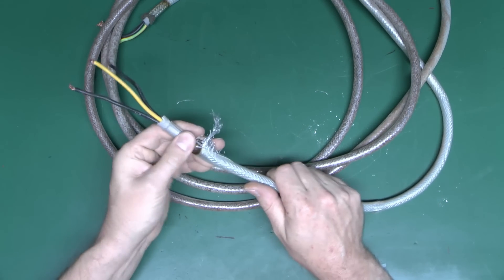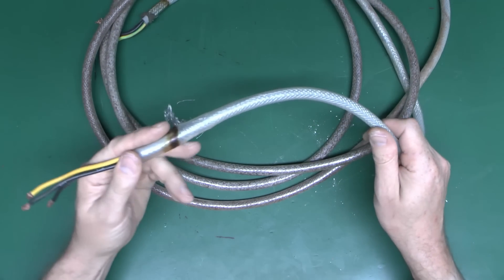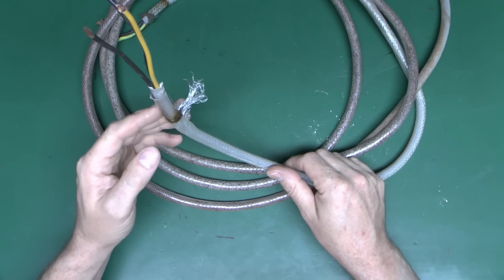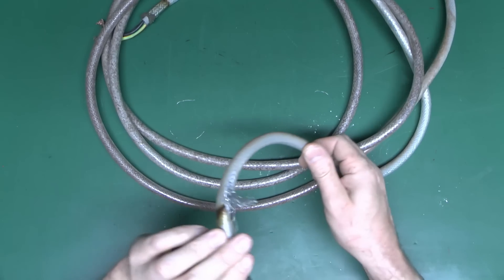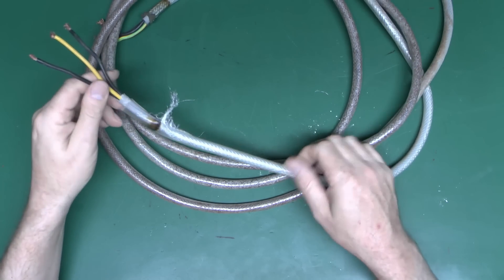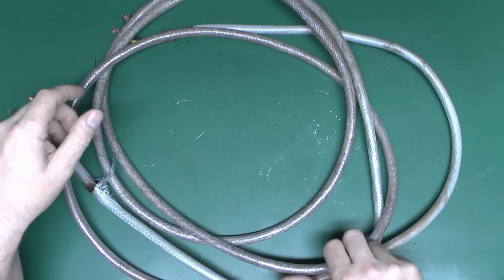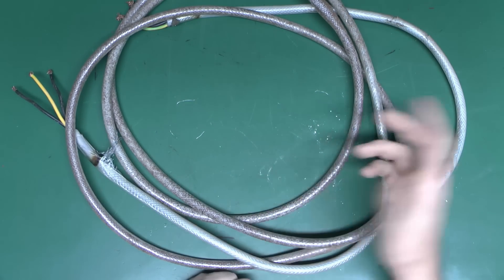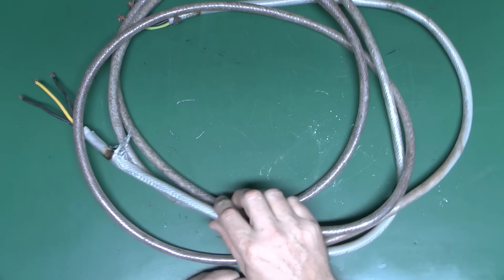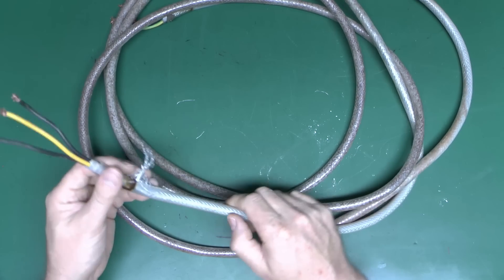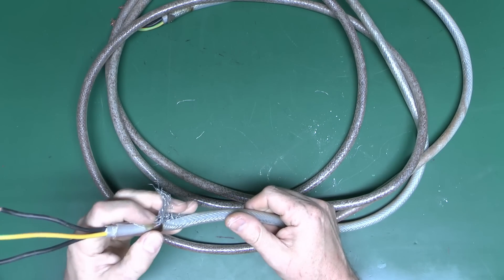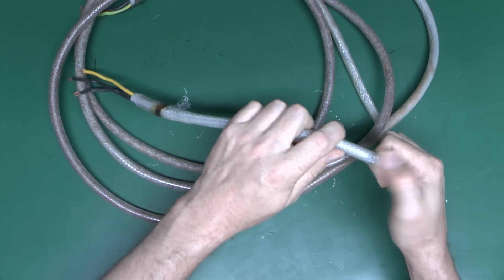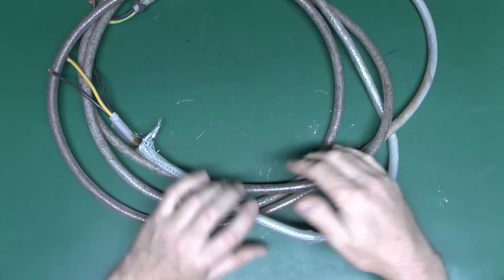So it can be used in a few things, but it is definitely not armoured cable. It's not suitable for use outside, and quite frankly it seems that 99% of the uses people seem to find with this stuff are completely inappropriate. And of course this is the kind of thing you would get. If you came across this on existing installation, say we're doing an EICR, then really this has to be coded up either as C2 or possibly further investigation. C2 in this case, because obviously it's just disintegrating and falling apart and is corroded, so not suitable for the installation.